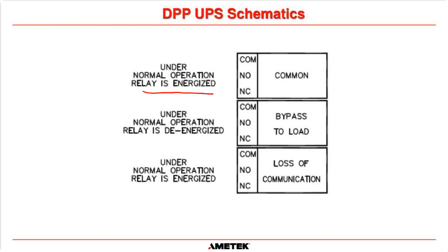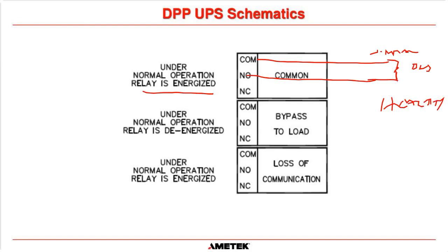So if under normal operation the relay is energized, we would then connect to the normally open and the common alarm, because when this energizes, that contact is going to be closed. So it's going to be closed in normal operation. So the DCS sees that as healthy. And it's only when this relay de-energizes for a fault, that contact there, let me erase that, will open, and the DCS will give an alarm. Okay.